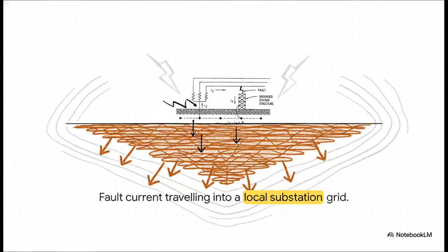But here is the tricky part. These grids have to be meticulously calculated and fully designed before a single drop of concrete is ever poured. Because you obviously can't test a copper grid that hasn't been built yet, engineers have to predict exactly how the natural earth is going to behave. They use what's called the Wenner 4-pin method. By driving 4 probes into the virgin soil at equal distances and passing a current between them, they measure the earth's natural apparent resistivity. This one critical data point is the absolute foundation of the math that dictates how much copper mesh is needed, how deep it has to go, and how thick the crushed rock on the surface must be to keep workers safe.